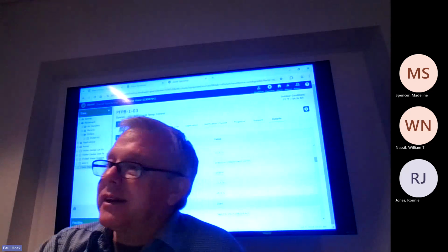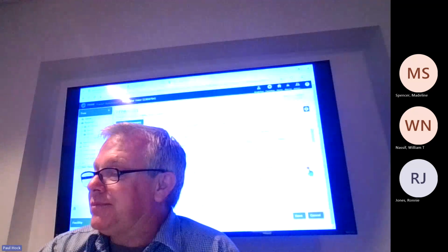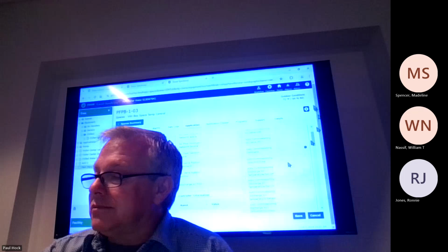I don't like to put that on the graphic because sometimes people just go in there and they keep clicking on it, and well, it's not working. If it doesn't work after the first time, it's not going to work. Or you can hit applications and this little gear right here. You click on it. It doesn't seem like it does anything, but once you click on it, it's going to throw the box into a calibration mode, and it's going to go through and auto commission it. And that's just for that one individual box.